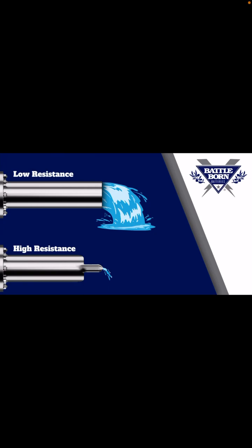Another example would be you're getting a switch that keeps going bad, keeps burning up, but it's rated for the amperage that you're supposed to be getting on that circuit. But for some reason, something's causing that switch to burn out over and over again. You keep replacing it, it just keeps doing that. Well, it could be that the connector is loose. So maybe the connector is what needs to be replaced. It's causing resistance, which is causing heat, and it's causing that switch to burn up.